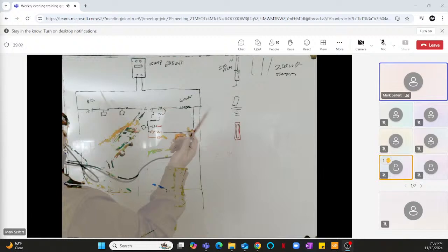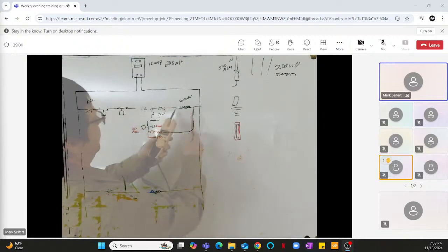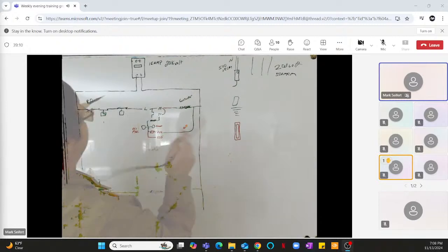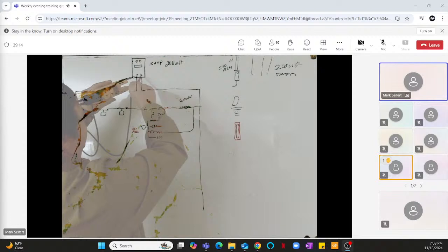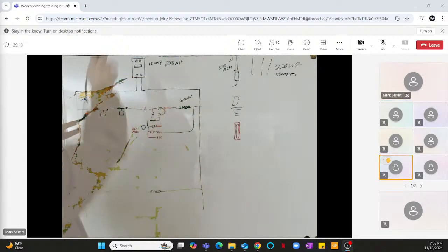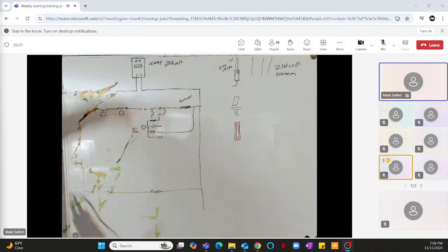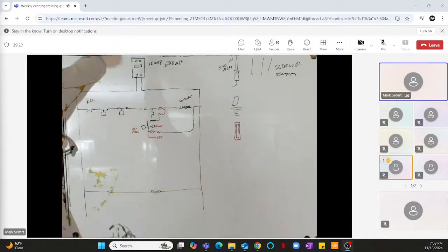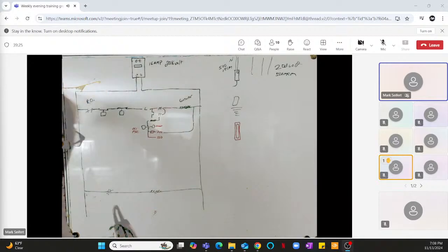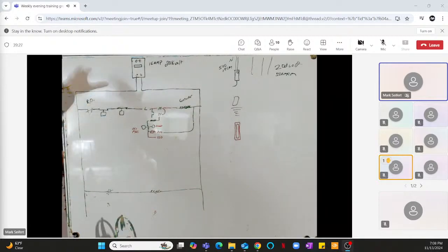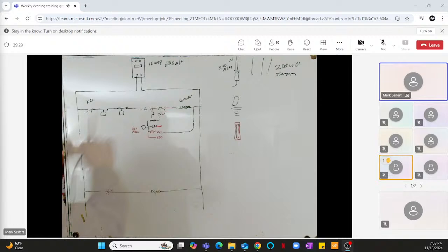Most of the time you come up to a compressor, it's off. You're going to try to figure it out. You're going to put your leads here. Well, you're going to check your breaker. Always check the simple stuff. Start with the simple stuff. Check your control power. Do you have 208? Yes or no? No? Go that way. Find it that way. Something's wrong that way. Yes? Something's wrong this way. Okay? First things first, check your power.